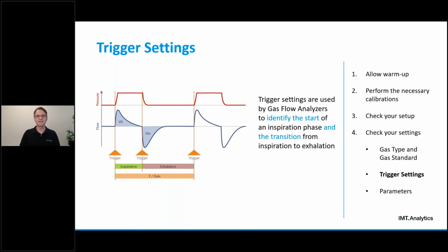Trigger settings are necessary for the gas flow analyzers to calculate the so-called breath-based parameters, such as tidal volumes, respiratory rate, or PEEP, which means positive end expiratory pressure. These are all parameters that are related to the breath phases. Without triggers, gas flow analyzers can't measure these parameters and typically don't display them or indicate something like no trigger on the screen. Most gas flow analyzers also have a trigger indicator on the display that indicates each time the analyzer is being triggered. For example, you will see later in the demo on IMT Analytics analyzers, there is a T flashing up on the display whenever a trigger is detected. So if you don't see the trigger indicator, and if your analyzer is not able to measure the breath-based parameters, this means that your trigger settings are not suitable for your current application.